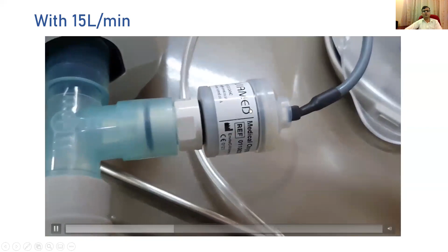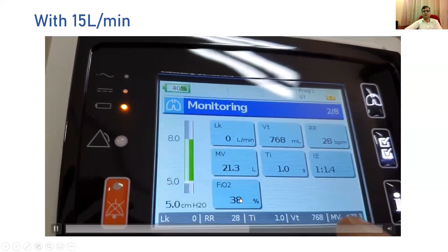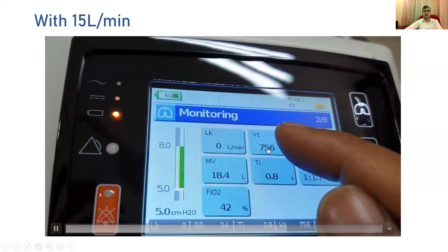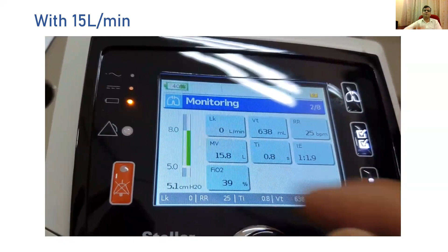So I have this oxygen sensor attached, so I can monitor the oxygen concentration. You can see I'm having no leaks and I'm breathing okay, but my FiO2 is hanging around 37, 38, maybe up to 40%. It all depends on the tidal volume and how fast I am breathing. If I slow down, I might get a higher concentration, but if I try to breathe more, the ventilator will recruit more air to get that pressure.